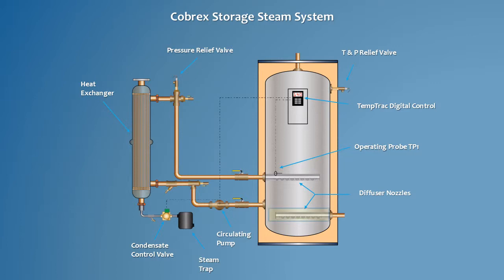The storage tank includes a diffuser nozzle on the inlet of the tank and on the circulation return fitting to the tank. The diffuser nozzle is designed to reduce the velocity and directionality of the inlet streams to the tank. This prevents disturbing the tank's naturally occurring stratification of heat to provide a more uniform tank temperature, as well as ensuring the heat exchanger is provided with the coldest inlet water, increasing the efficiency of the system. The diffuser is designed into a bolt-on flange for easy removal, maintenance, and cleaning.